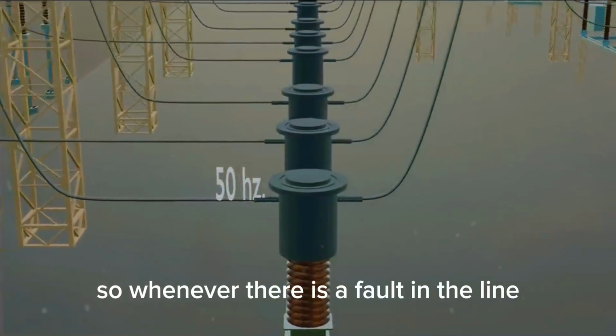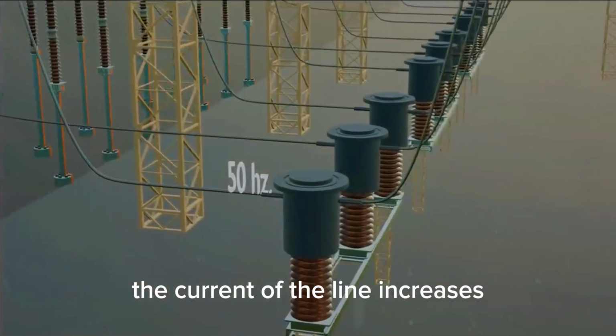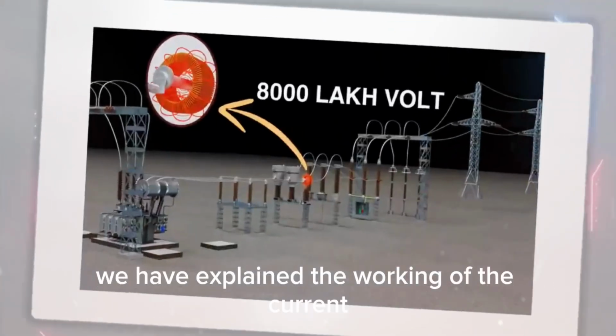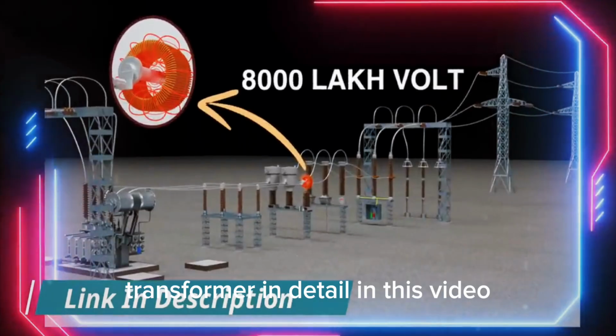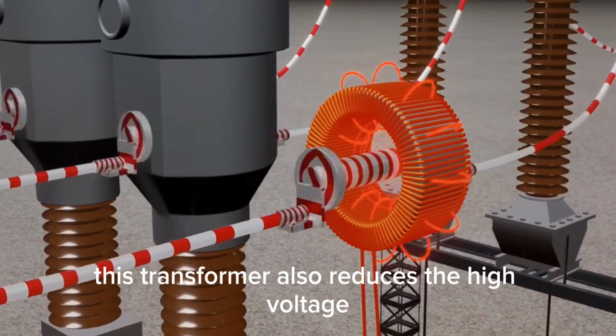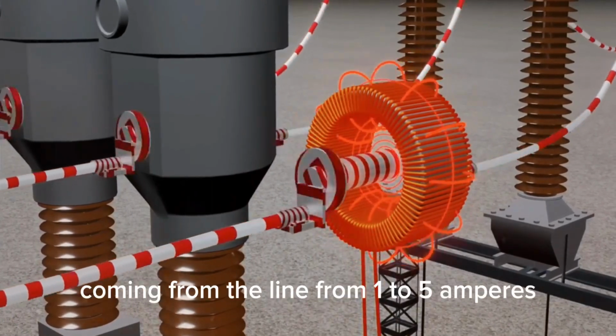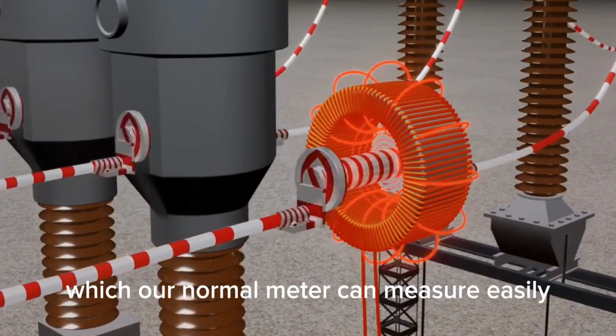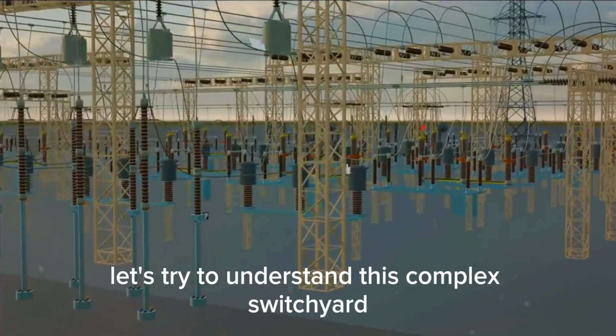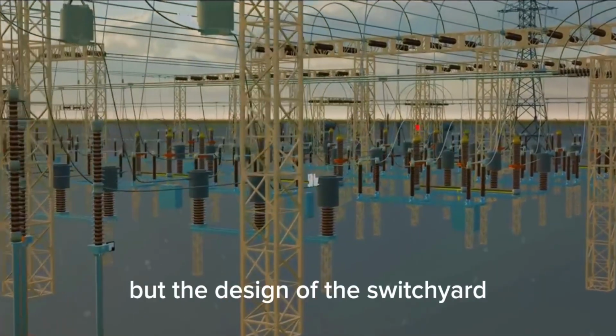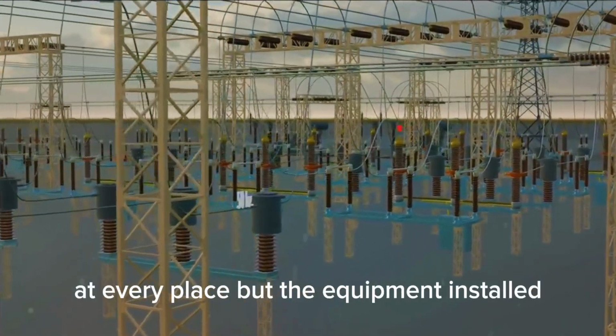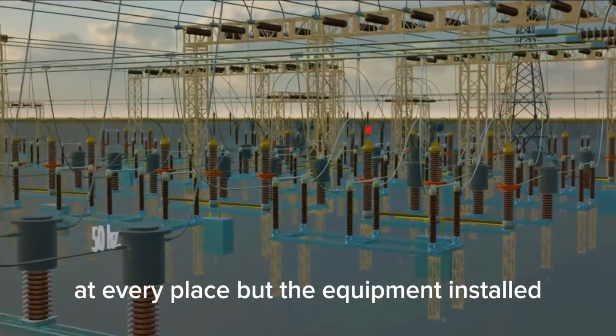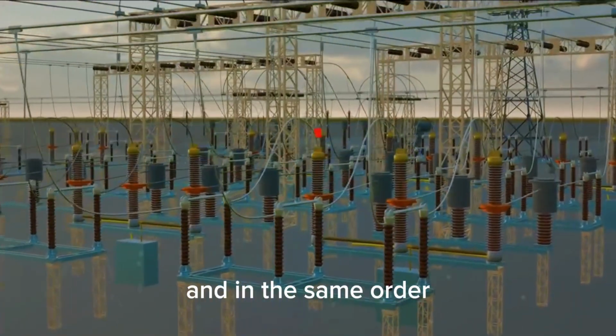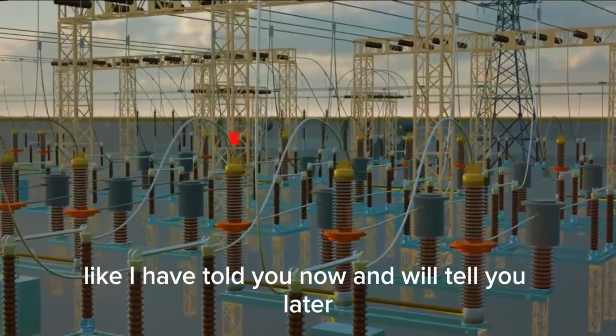It basically measures the current of the line. So, whenever there is a fault in the line, the current of the line increases and it measures this fault current. We have explained the working of the current transformer in detail in this video. You can see it here. This transformer also reduces the high current coming from the line to 1 to 5 amperes, which our normal meter can measure easily. Now from here let's try to understand this complex switchyard, which is actually very simple. But the design of the switchyard can be slightly different at every place. But the equipment installed, they are installed in the same way and in the same order, like I have told you now and will tell you later.